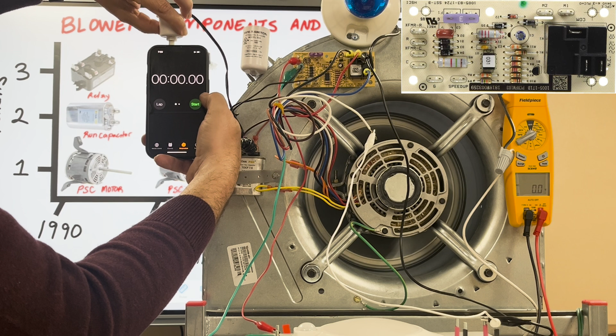And this float switch was the easiest way to break my G call and hold my stopwatch at the same time. So, and also show you this is pretty much what happens when your float switch would trip. I would wire it coming out of R on the board, and then out to the float switch. Out of the float switch, then I would wire to my thermostat. Now the thermostat gives a G call. That's why I'm hooking my float switch back up to the board, because in that theory I don't have a thermostat here.